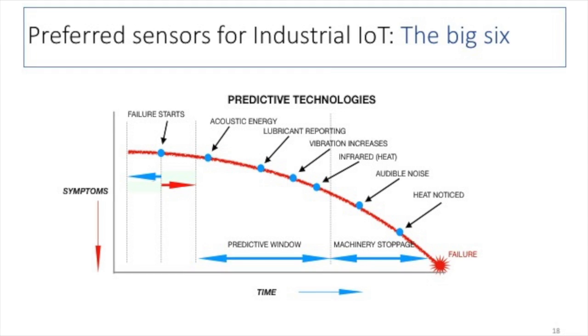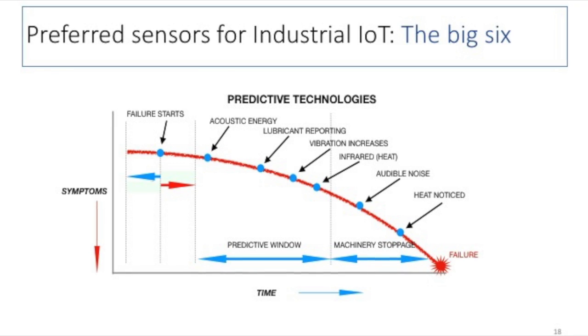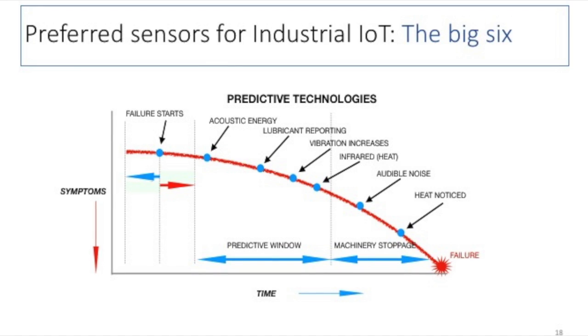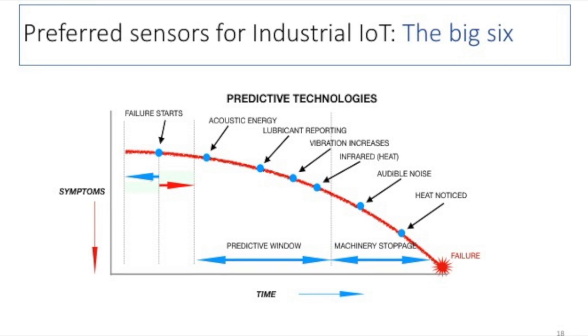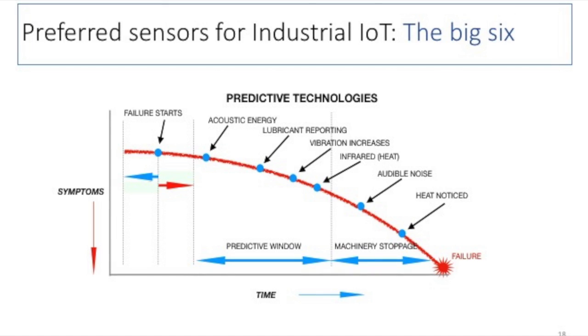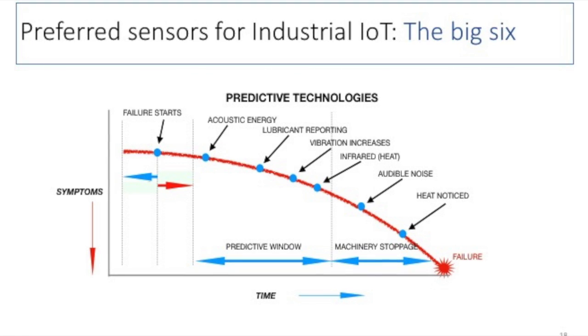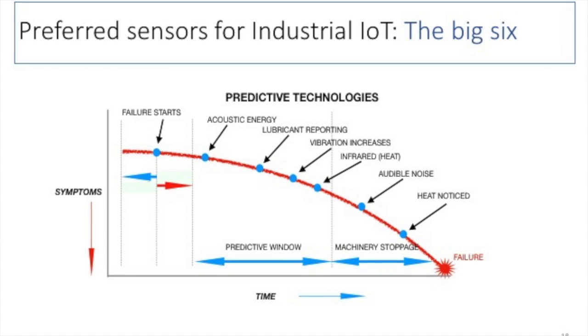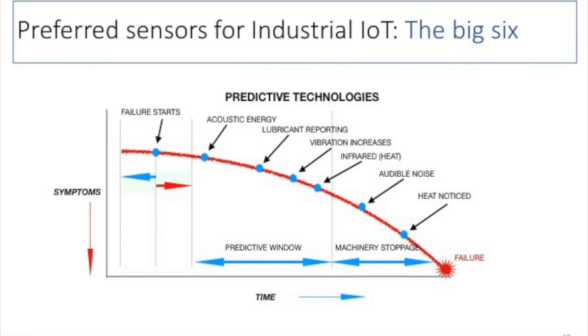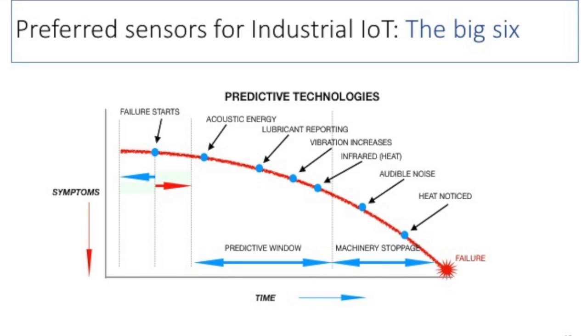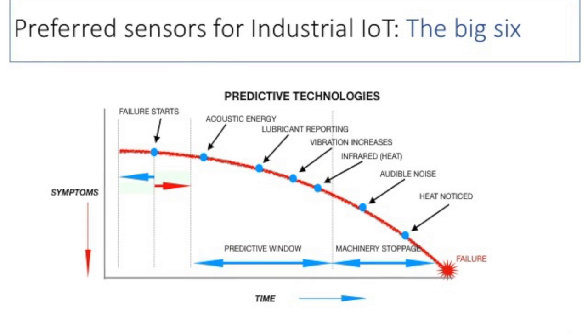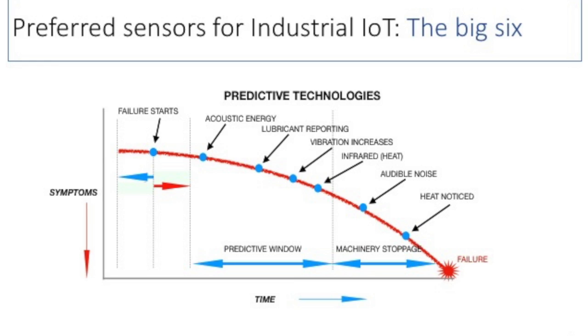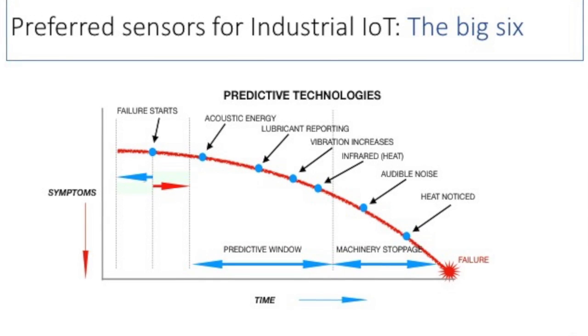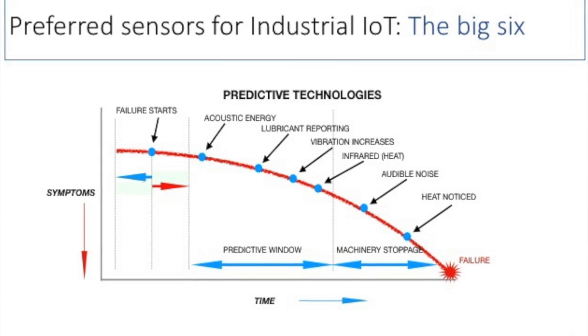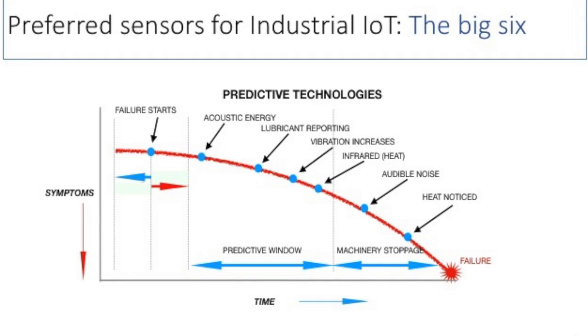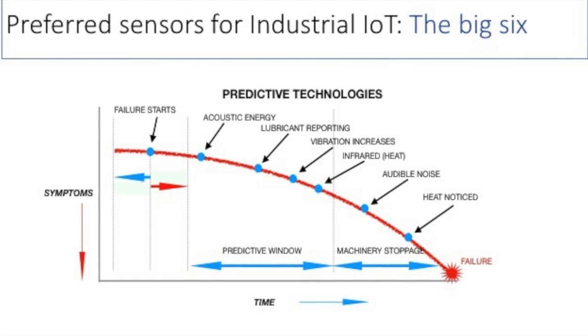The fourth is temperature sensors or thermal imaging sensors. In some machinery they can give a very good outlook on how bad the level of energy lost in inefficiencies is. When audible noise happens, it's usually way too late, and when you see smoke, the manufacturing process has already stopped. You can complement those sensors with current and voltage sensors, and also read a PLC that controls the production process in order to get more additional data.